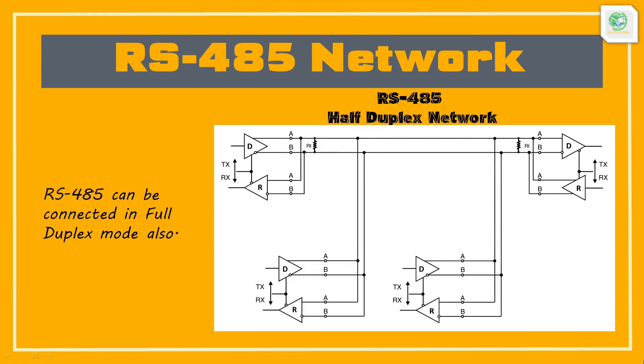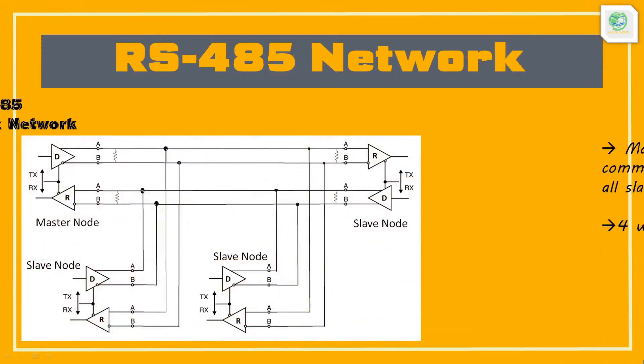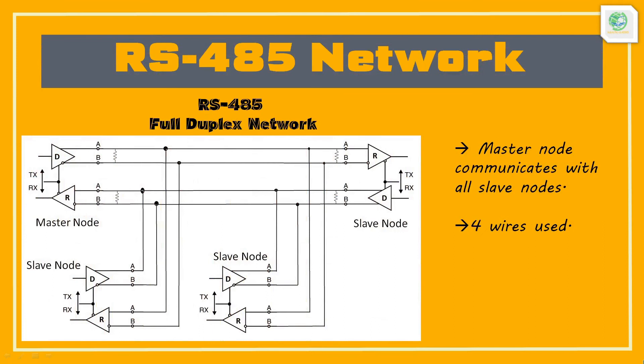RS-485 can also be connected in full duplex mode using 4 wires. In a full duplex type of connection, it is necessary that one node is a master node and all others are slaves. The master node communicates to all slaves, but a slave node can communicate only to the master. Two wires are for transmission from the master node and two wires are for reception at the master node. Terminating resistors are again installed on the two farthest terminals.